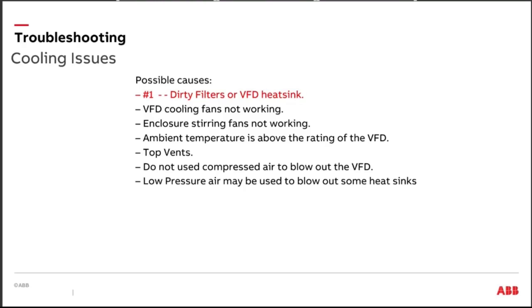You've not cleaned anything. And one of the worst things that could happen in this is that we had heavies or metal shavings that were heavy enough to stay in the bottom of that enclosure until you put that compressed air in there. And now you've lifted those heavies up and they're going to settle back down into the drive somewhere. That you absolutely do not want to do, ever. Okay? Now, not to talk out of the other side of my mouth. It might sound like it, but I promise you I'm not. If the heat sinks come out the back of the enclosure, you could use some low pressure air, compressed air, to actually blow the heat sinks out.